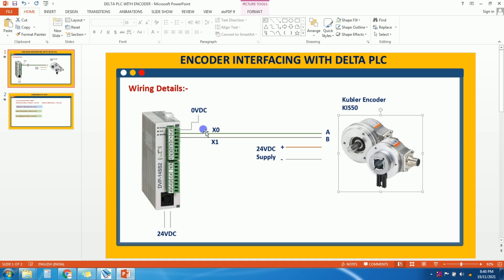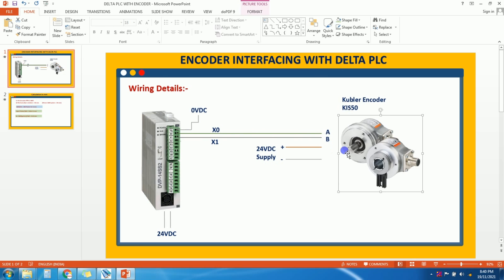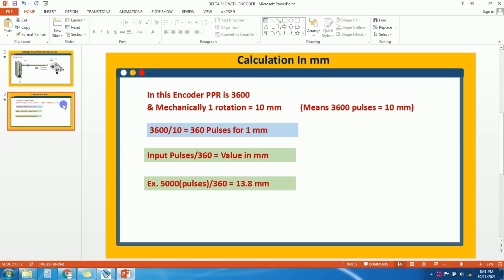On the encoder manual you can see which cables are for plus 24V, minus 24V, A and B. Connect A to X0 — the X0 input of the PLC — and B to X1, another input of the PLC. For the PLC input common (SS), give 0V, since this encoder has plus output from A and B. If your encoder gives negative output, A-bar and B-bar, then give plus 24V to the common input instead.